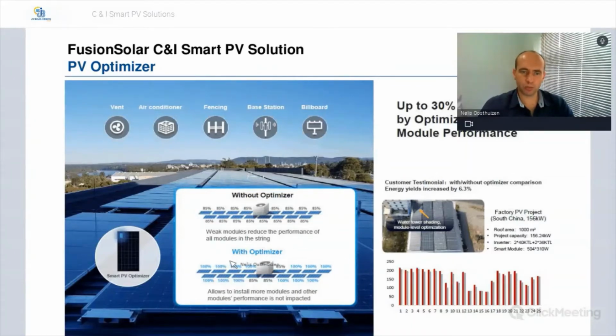But if you have optimizers present in the system, that 1 or 2 panels specifically, only they will perform at a reduced rating, but the rest of your string will just still perform as per normal. So the optimizers is definitely a solution that you should look at if you've got any of these possible problems on your site where shading can be caused by a vent, air conditioner, fencing, cell phone base station, or even a billboard that might put up some shade onto your system.